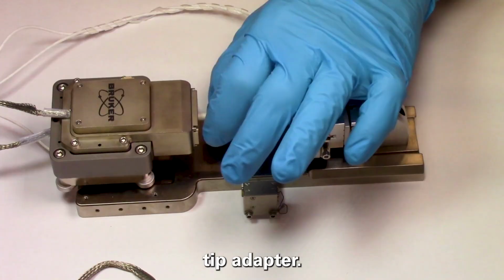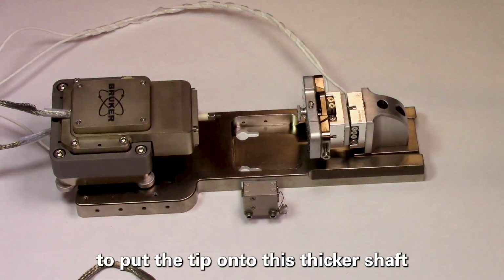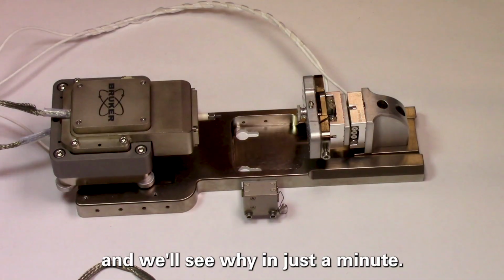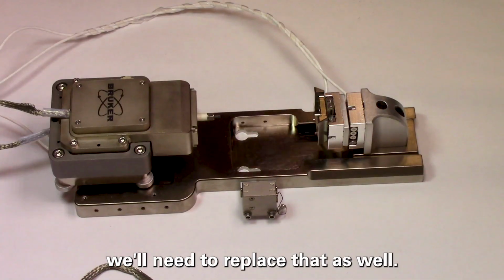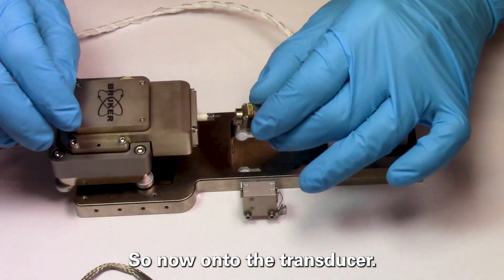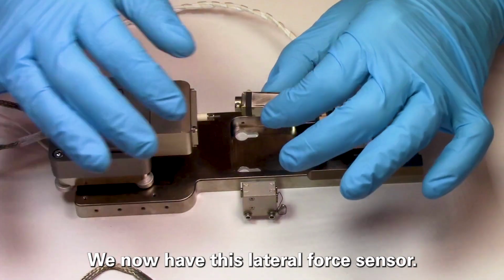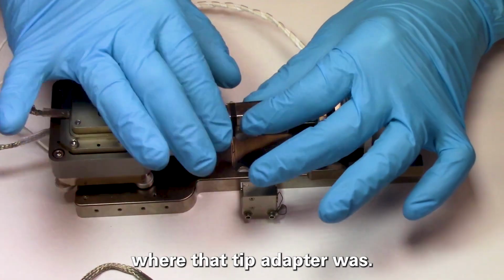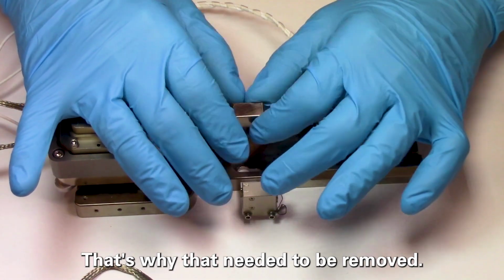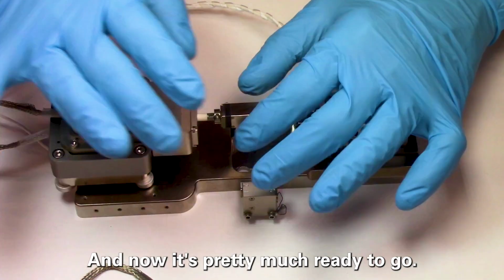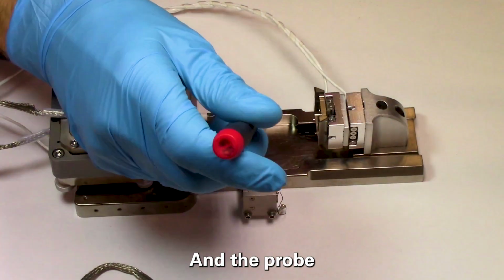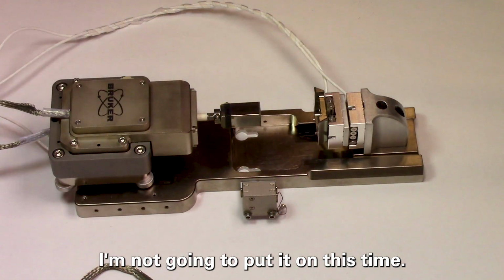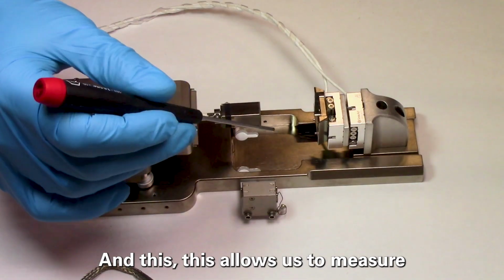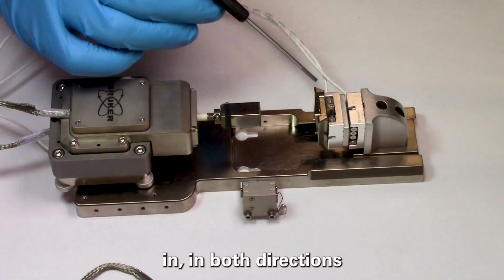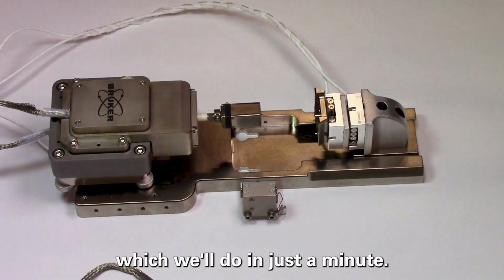And then I just need to remove this tip adapter that just allows us to put the tip onto this thicker shaft, and we'll see why in just a minute. And then as well, I'll also remove this sample holder since we'll need to replace that as well. So now onto the transducer, we now have this lateral force sensor. This just screws directly onto that shaft where that tip adapter was. That's why that needed to be removed. It just threads on here, and now it's pretty much ready to go. And the probe would just go on the end here. I'm not going to put it on this time. And this allows us to measure the lateral forces in both directions when we're doing some scratch tests, which we'll do in just a minute.